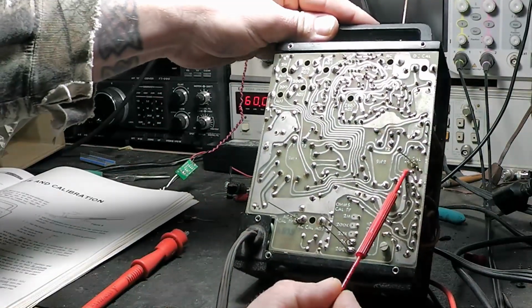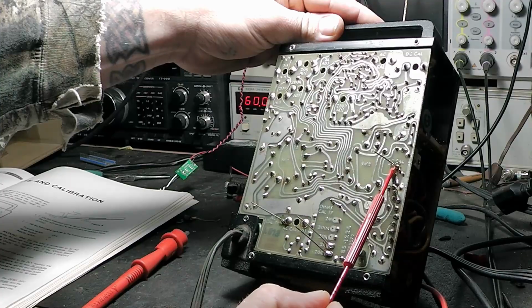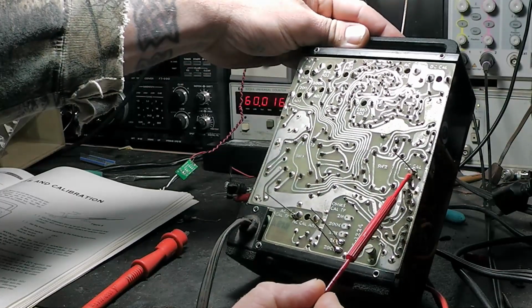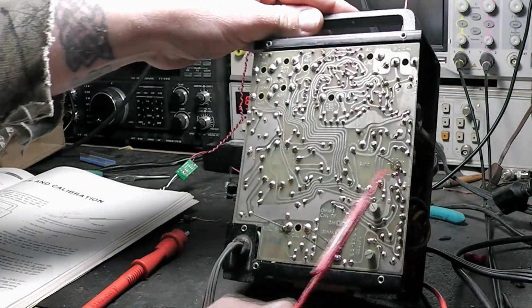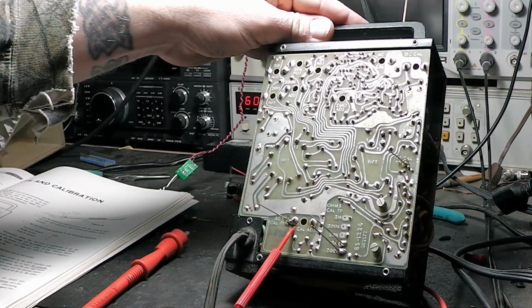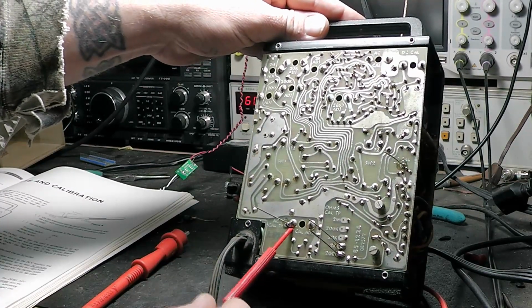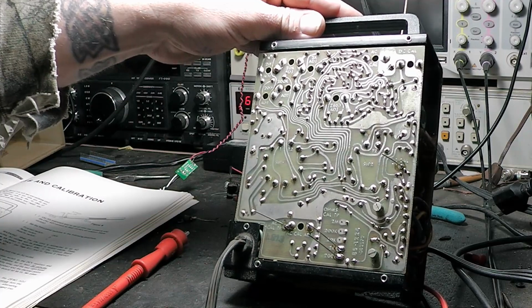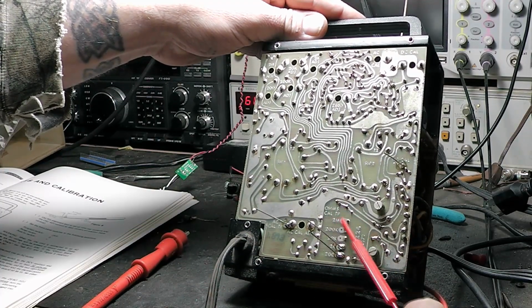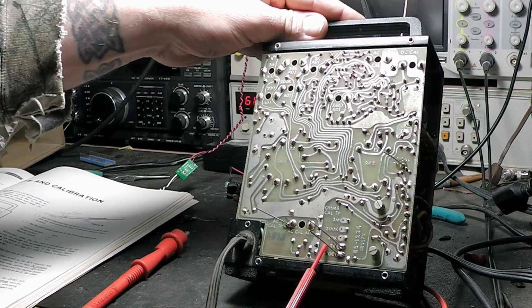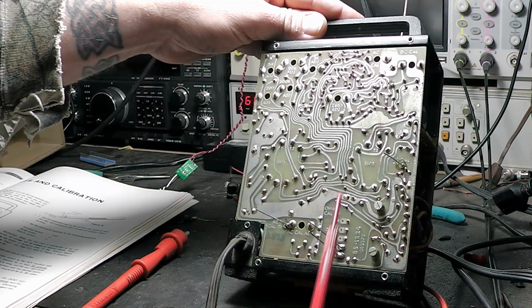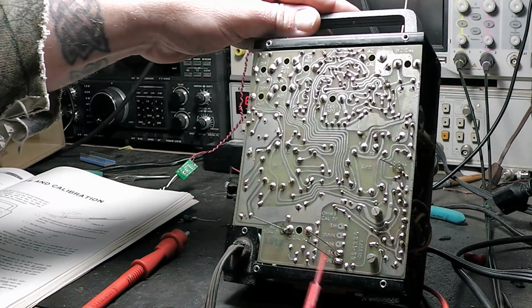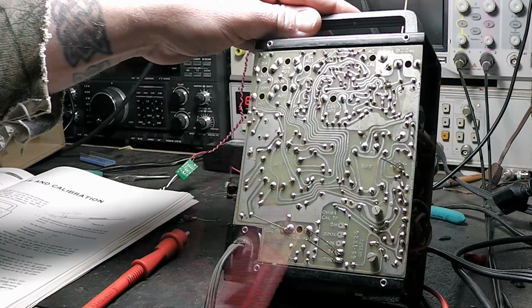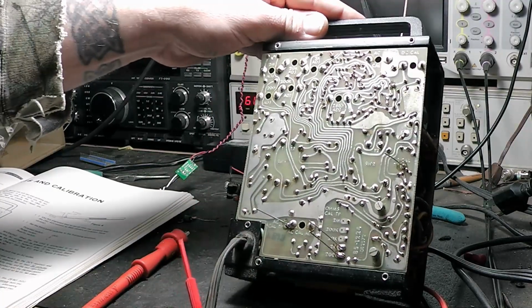If you've got one of these, you can reference as we're going along here. Right here's your DC calibration, where you put your tip. Over here is your AC calibration test point. And right here's your ohms calibration test points. You've got 200, 2K, 20K, 200K, and 2 meg. Now I've just got a couple here. I'm not going to go through the whole thing. Once I do a couple, you'll kind of see that.